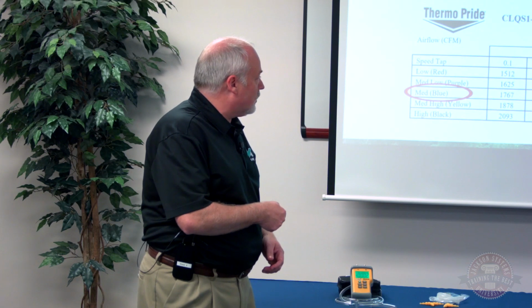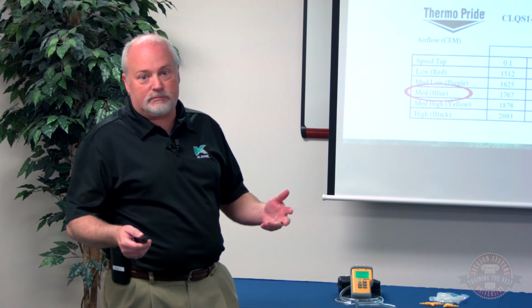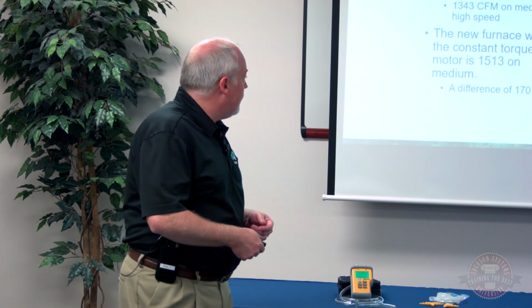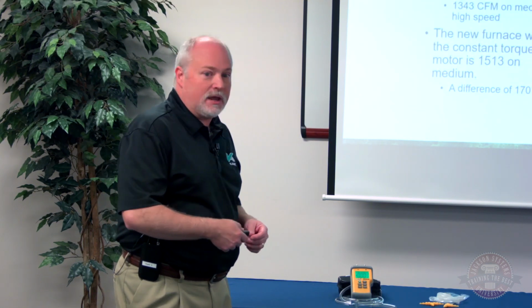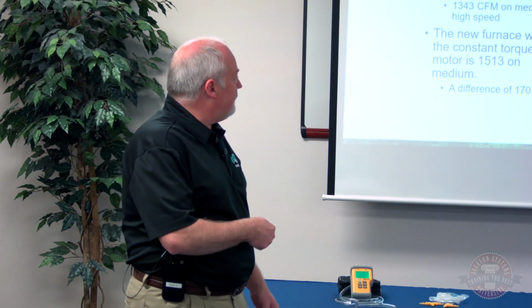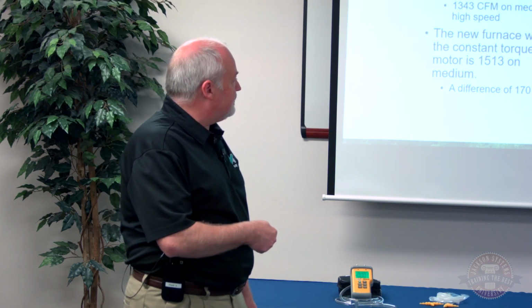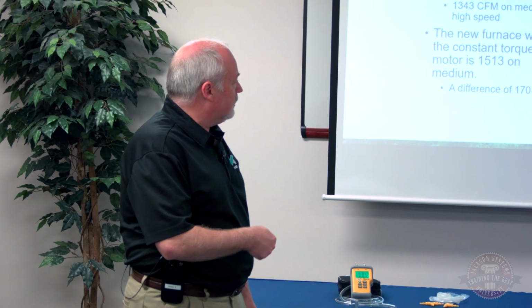Now, if we had just changed that out, and I should mention as well, this has the ECM constant torque motor coming next year in 2019. That's a requirement. All your equipment, you're going to start seeing with ECM motors on it. So this is something to pay attention to, because if I go out on an older piece of equipment, this is one I just happened to pull up as an example, at that same 1/2 inch static pressure on medium speed, this PSC motor moves less than 1,400 CFM of air, the same external static pressure.